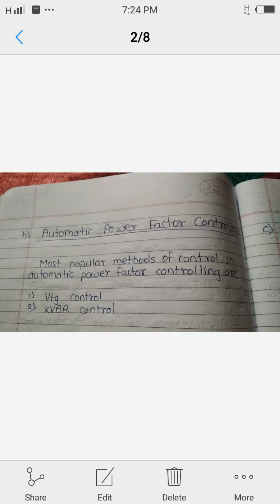Now see the automatic power factor controller. In electrical power systems, power factor control has long been accepted as an important step to energy conservation. म्हणजेच काय तर पॉवर फॅक्टर कंट्रोल करणे म्हणजे ही एक खूप मोठी स्टेप आहे एनर्जी कन्झर्व करण्याची. Capacitors are switched in and out of the system according to need of VAR compensation. If properly applied and controlled, capacitance improves performance of distribution network as it provides a reactive current locally and offers the advantages of lower losses, improved line voltage and reduced utility penalty, hence lessened billing charges.